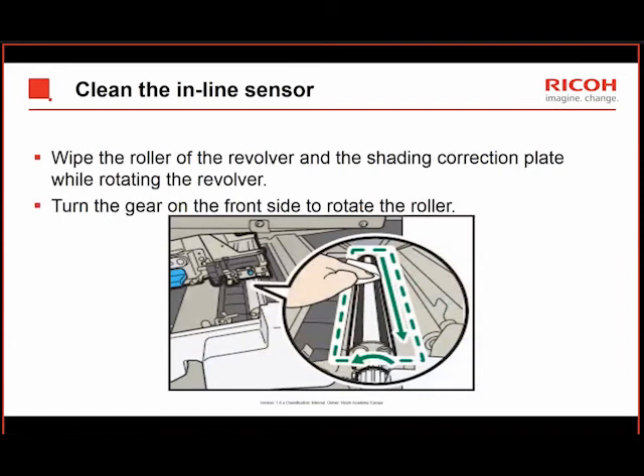Oh, yeah, there we go. There's the roller. So you can see here, this is the roller. There are white plates on it. You can see here the 2 black rollers. There's a grey shading correction plate on it, and then underneath you can't see, but there are also 2 white rollers underneath. So when you clean it, you need to turn this gear at the front, just a drive gear. You can just turn that by hand, and then you'll expose the other rollers underneath.